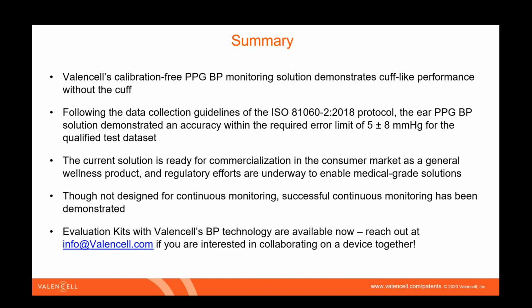But this particular calibration was simply meant as a proof of concept, to say, if you took a measurement on day 1 and you said, here's my offset, and you kept that offset all the way through the rest of however long that calibration lasts, which we know doesn't change at all over at least a month, then you're good to go. Gotcha.